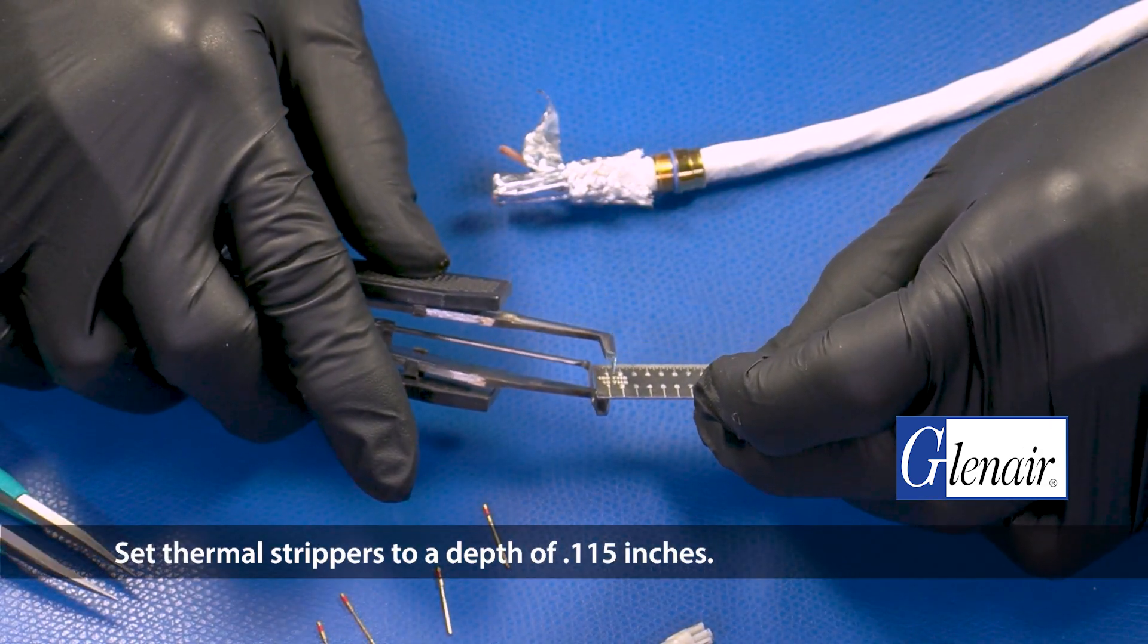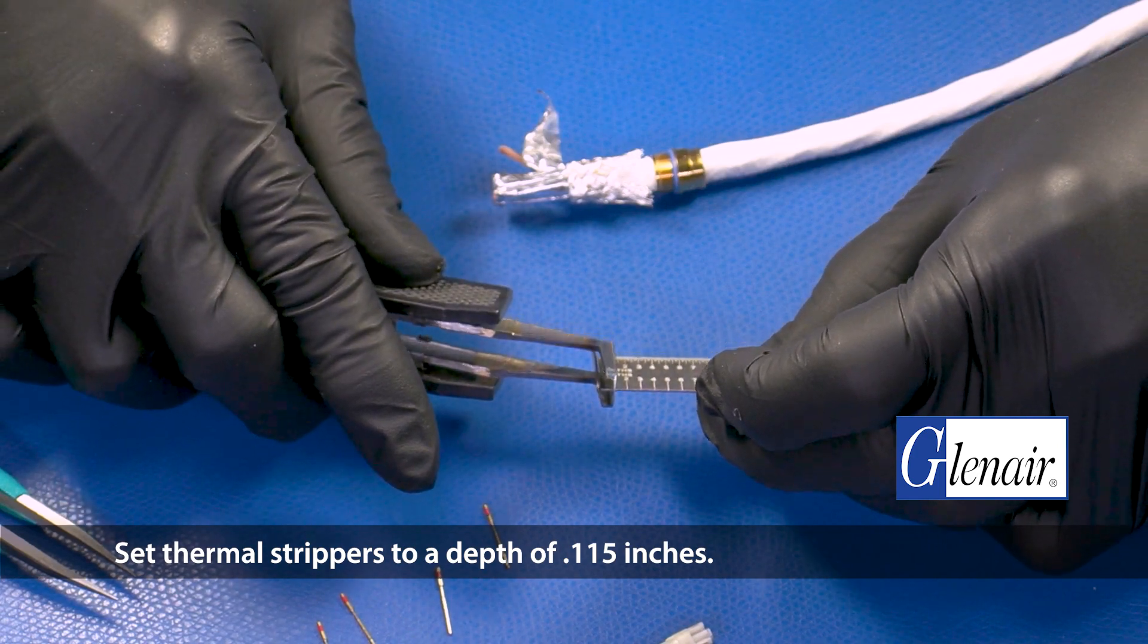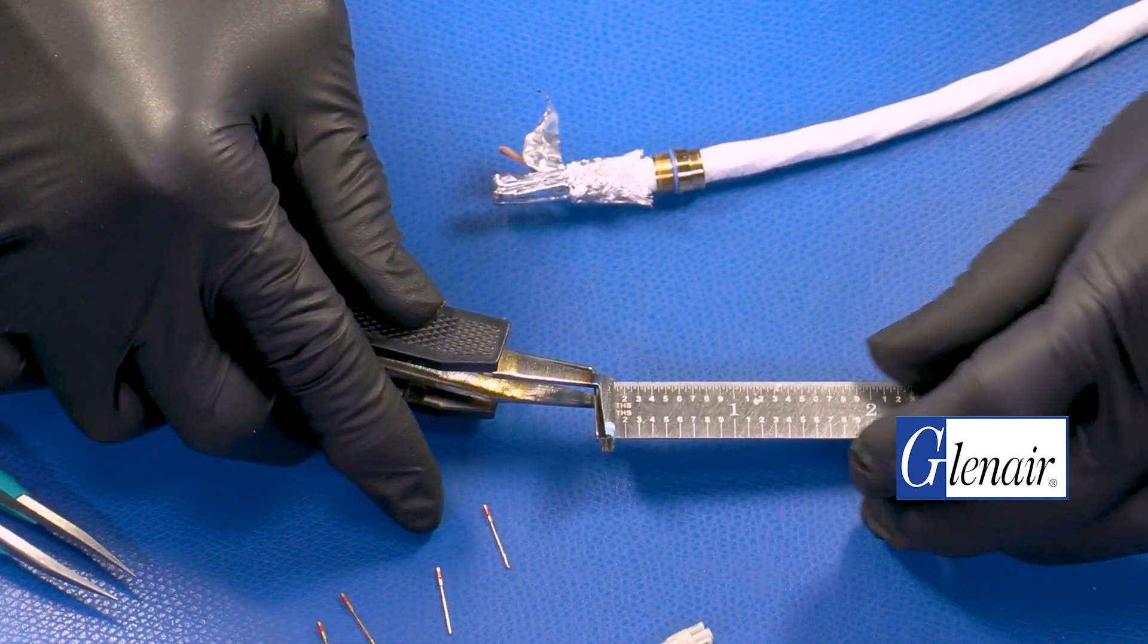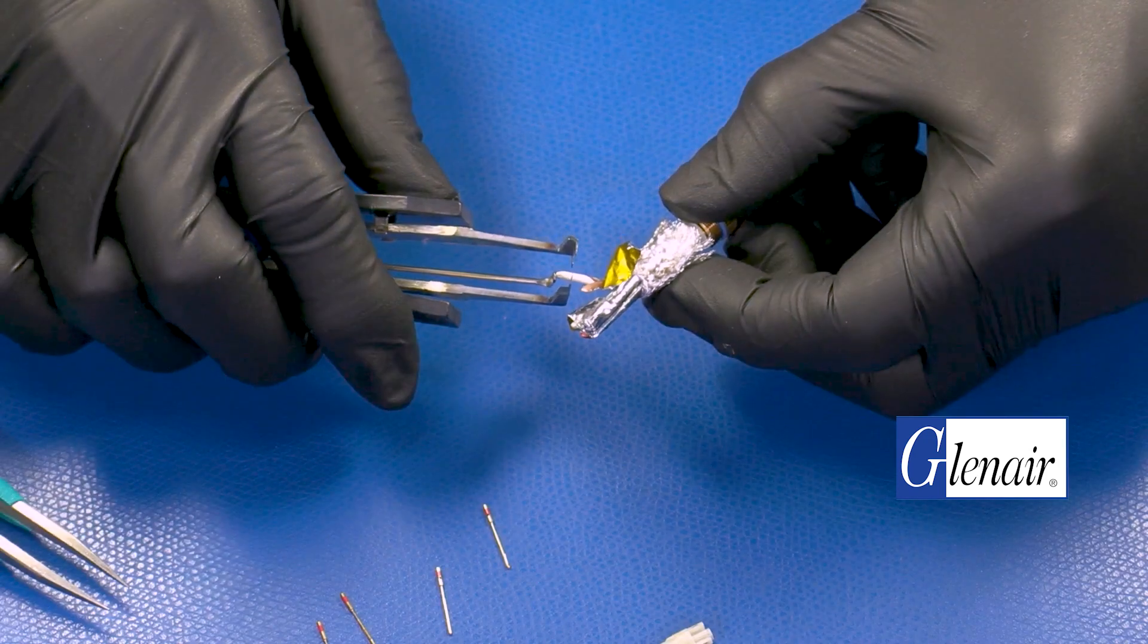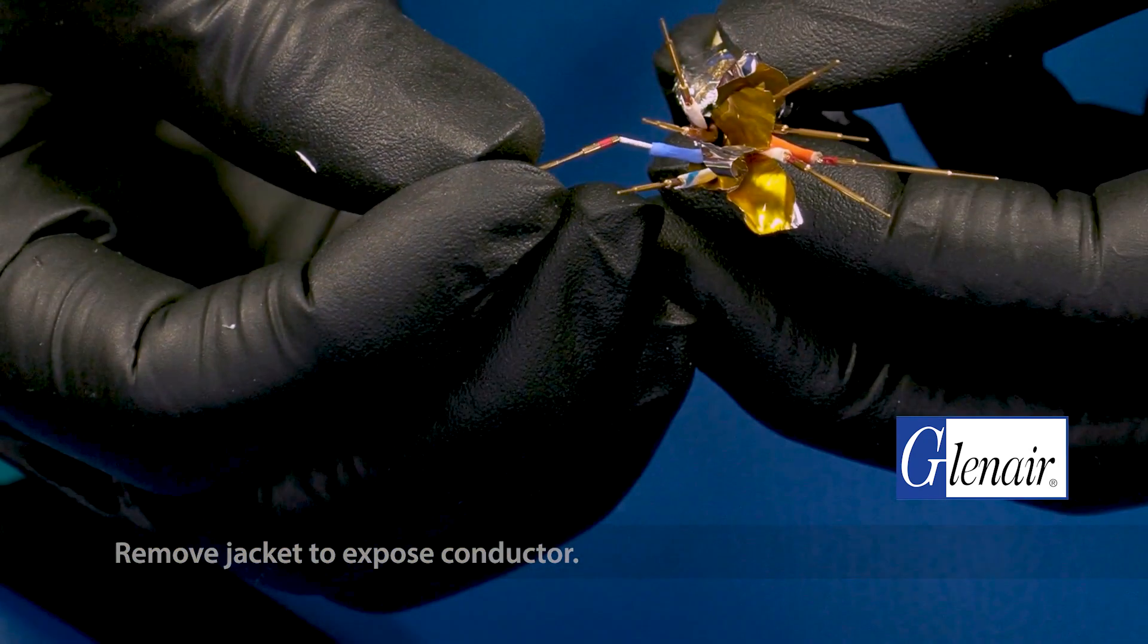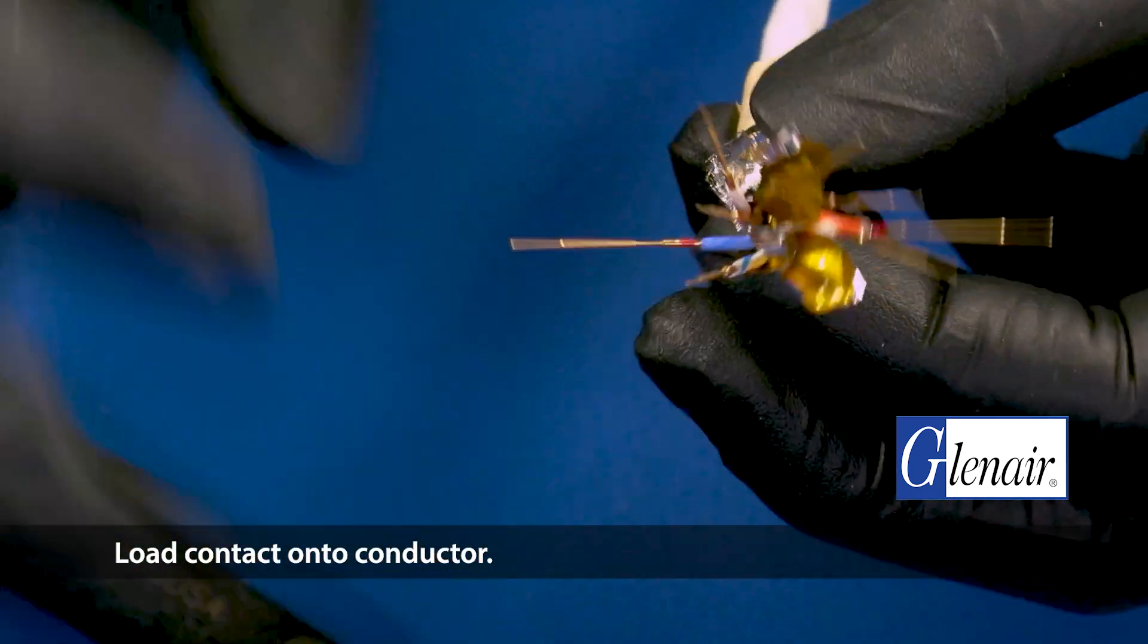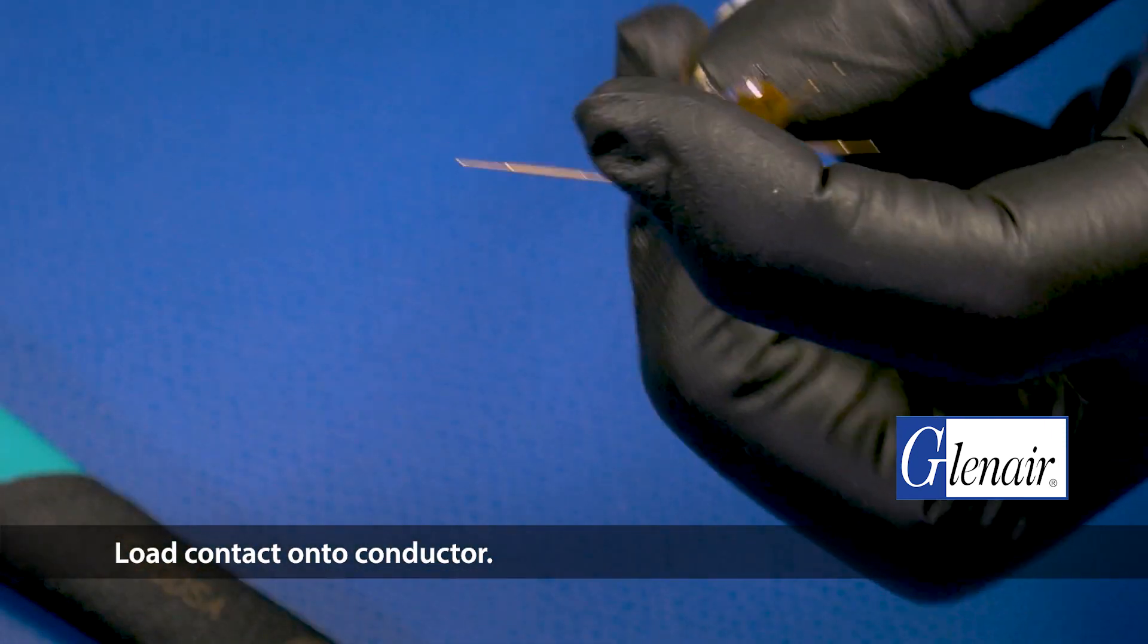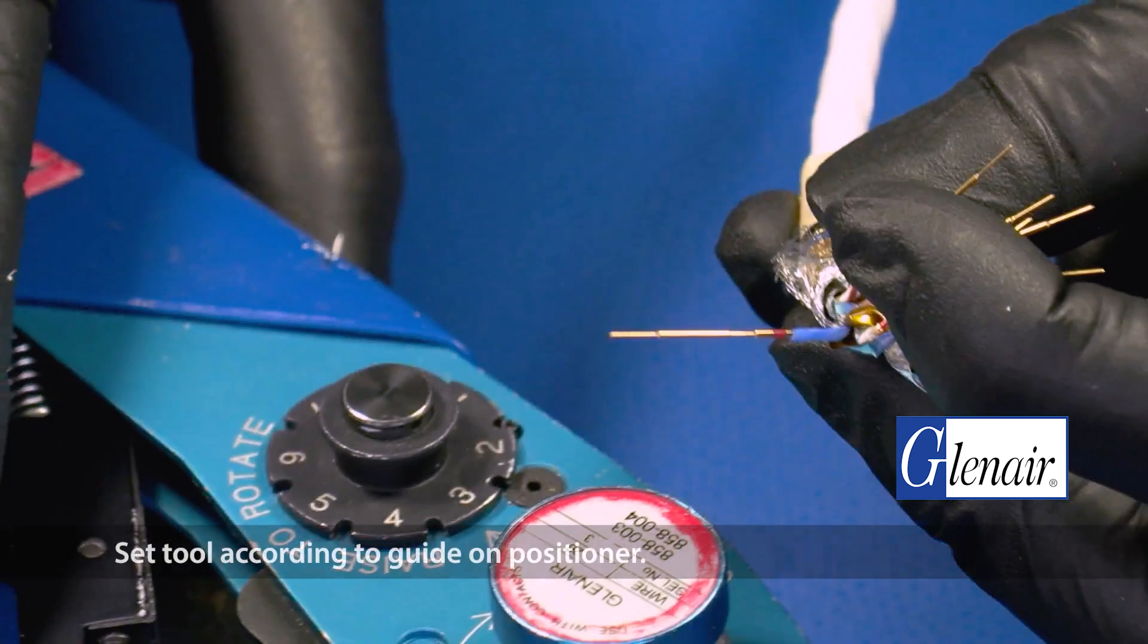Set thermal strippers to a depth of 0.115 inches. Remove jacket to expose conductor. Load contact onto conductor. Set tool according to guide on positioner.